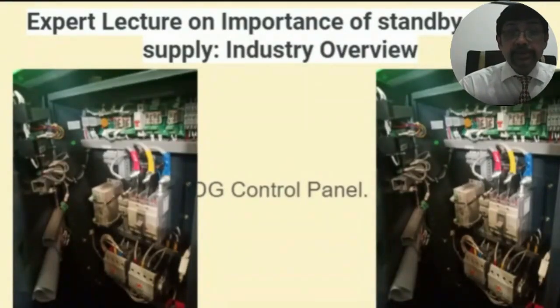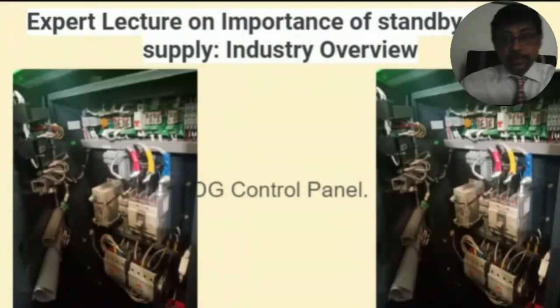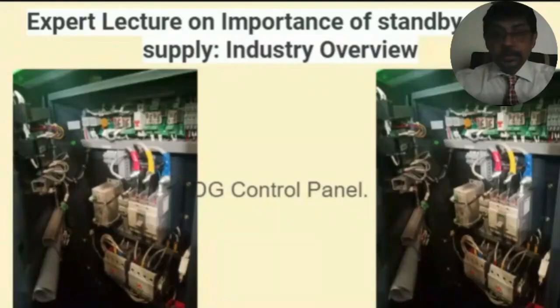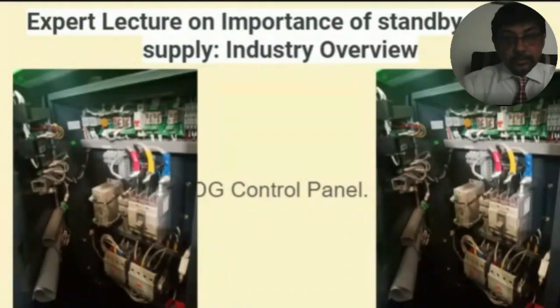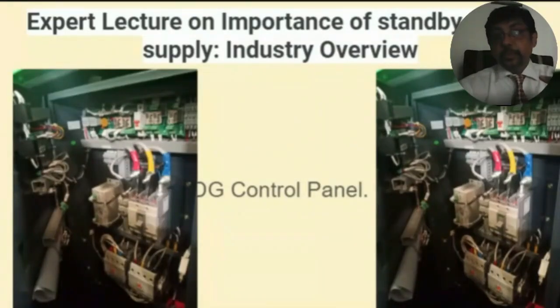Now this is the DG control panel for an automatic system. For an automatic system, we have two incoming supplies. The first, on the top, we can see is an MCCB. This MCCB takes the cable coming from the gensets to the control panel, and from this MCCB it goes ahead. At the same time, we have two contactors below the MCCB, which function automatically for auto changeover, auto start, and auto stop. These are the two contactors which are functioning there.